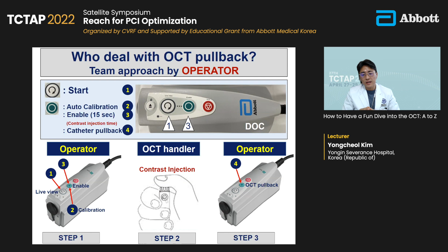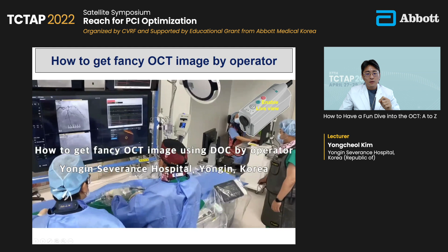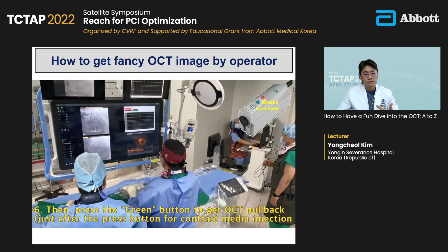So let's have a look at how the operator gets a fancy OCT image. You can see the button box called the DOC. It enables the operator to control every single step of OCT image acquisition, not the OCT machine handler. The first step is to press the live button, and then you flush the catheter to clear blood inside the OCT catheter by contrast media, not saline. The next step is to press the green button to get the auto calibration. Then the OCT handler is involved only 1 time in the OCT pullback process, for the injection of contrast media. Next, just press the green button twice to get the fantastic OCT image.